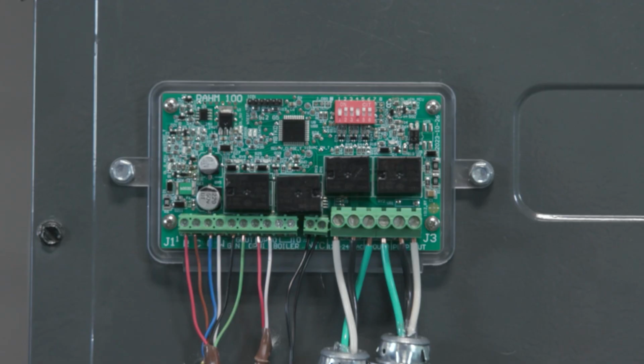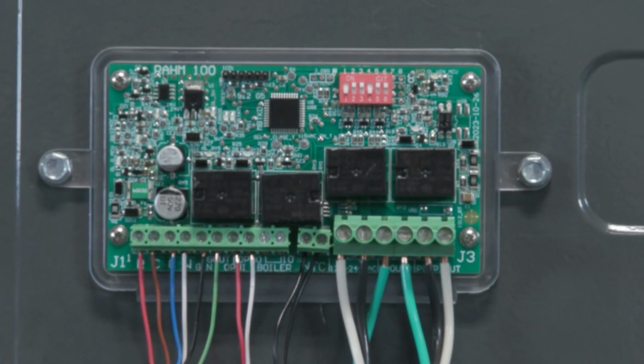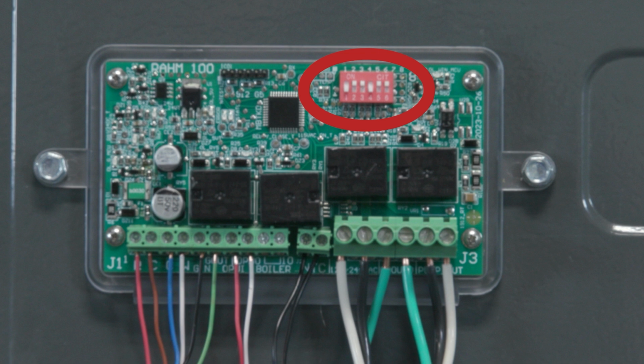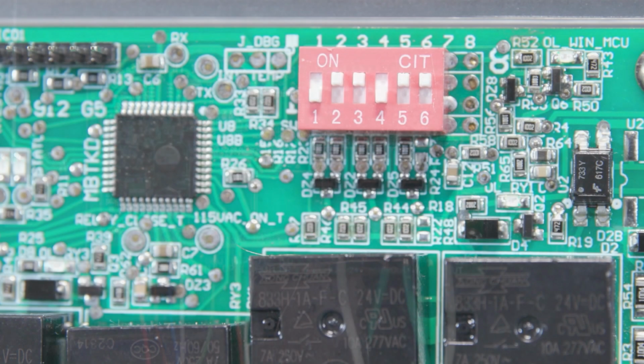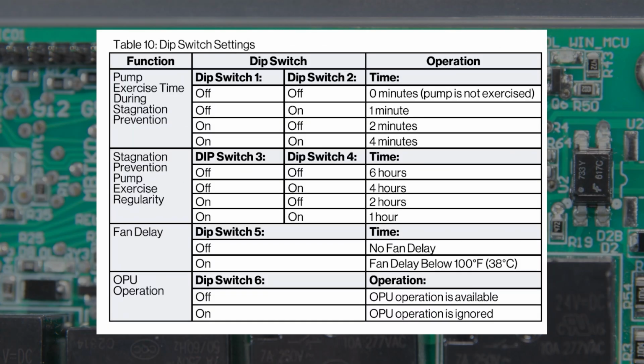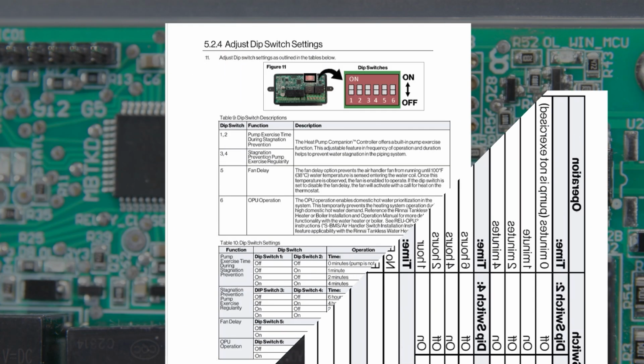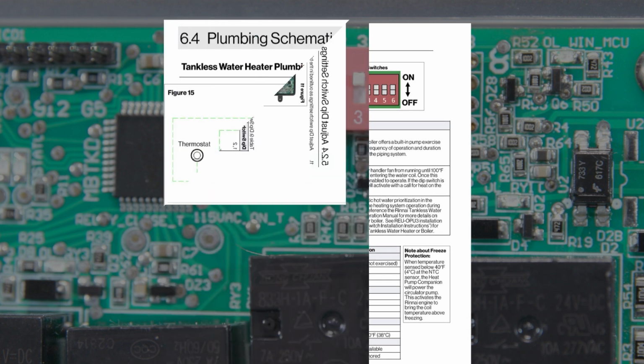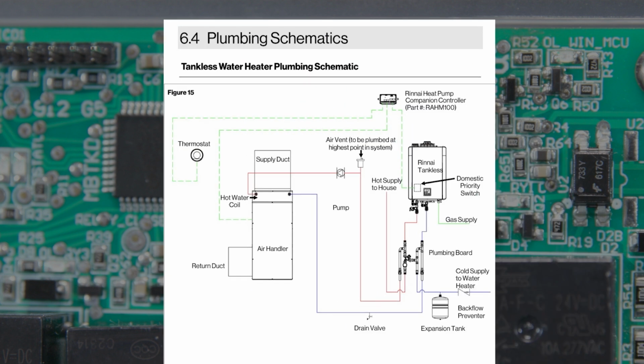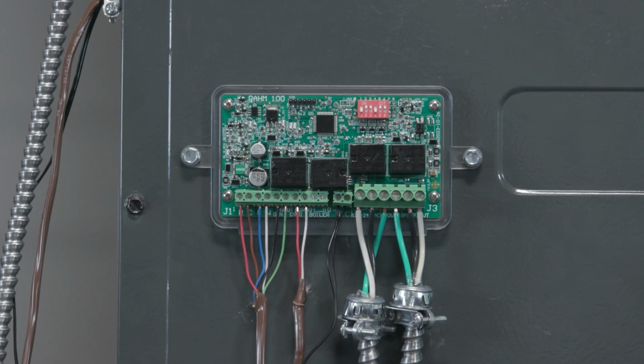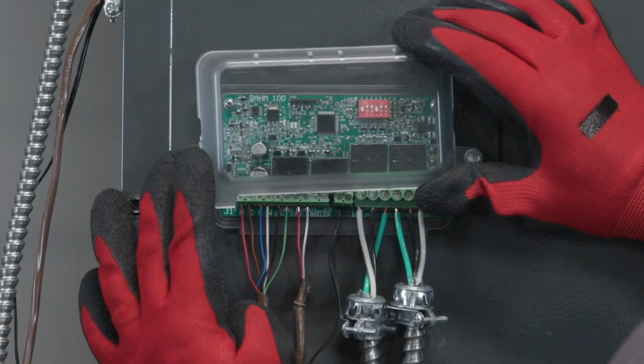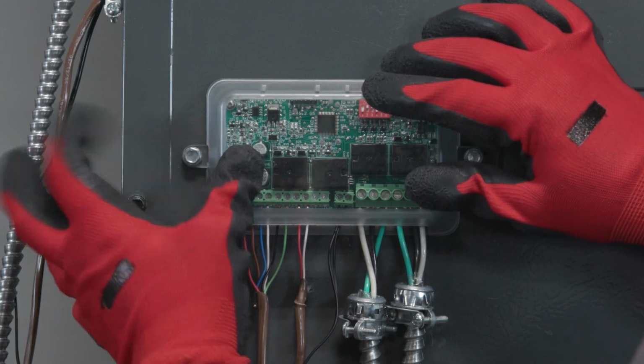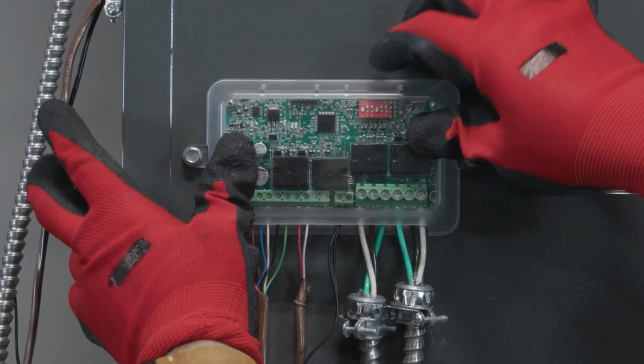Now let's adjust the 6 dip switches in the red box on top of the controller board. The first 4 switches adjust the pump exercise settings. This helps prevent water stagnation during times of low usage. Reference the manual to determine the preferred dip switch settings. Wiring connections and a plumbing schematic are also laid out in the instruction manual. It is critical the dip switches are set correctly for the unit to function properly. And don't forget to snap the plastic cover back on when you're done.